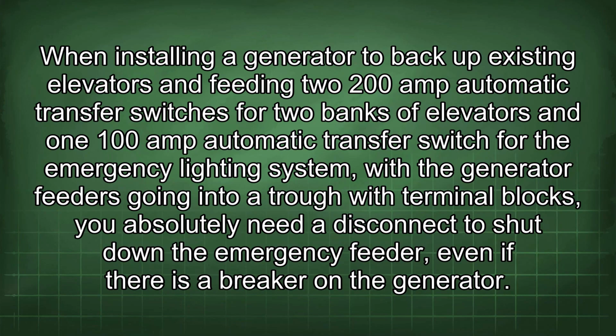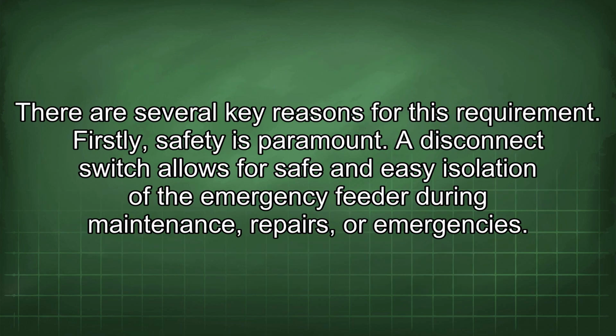When installing a generator to back up existing elevators, feeding two 200-amp automatic transfer switches for two banks of elevators and one 100-amp automatic transfer switch for the emergency lighting system, with the generator feeders going into a trough with terminal blocks, you absolutely need a disconnect to shut down the emergency feeder, even if there is a breaker on the generator. There are several key reasons for this requirement.